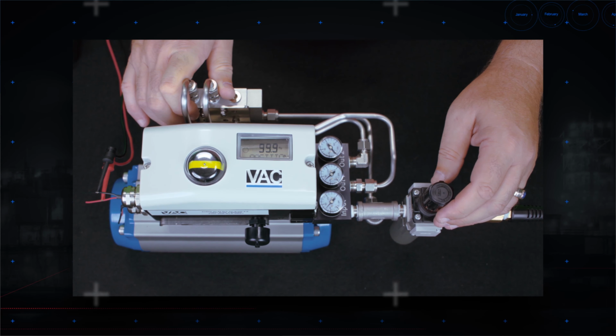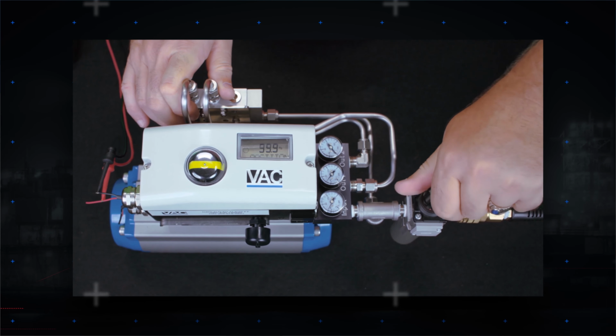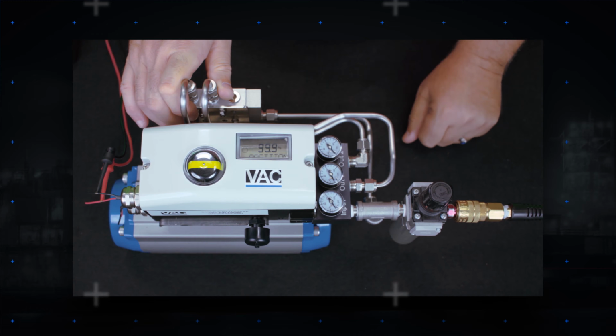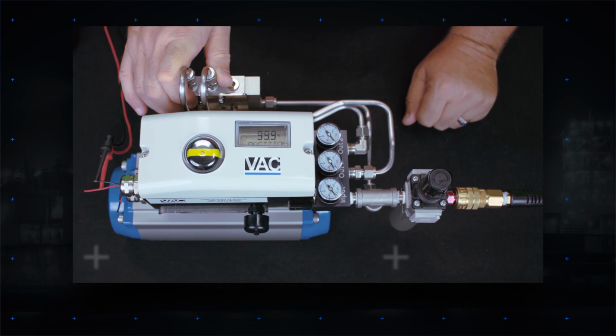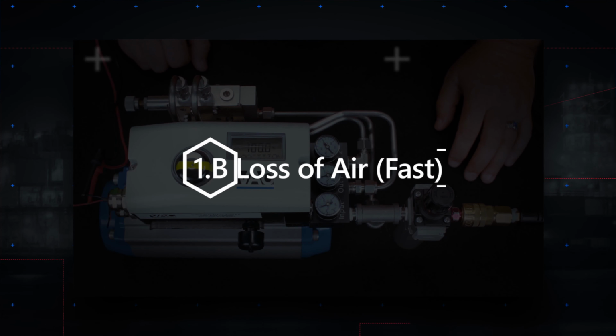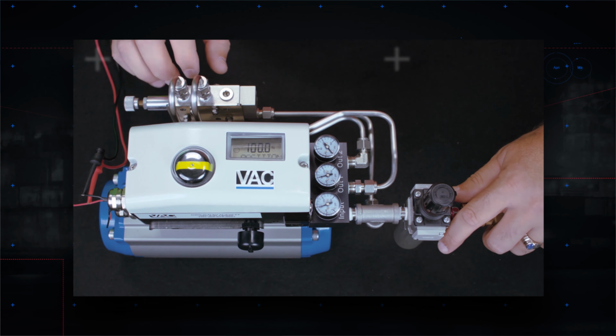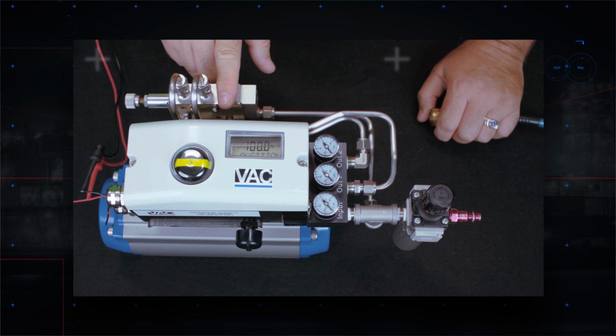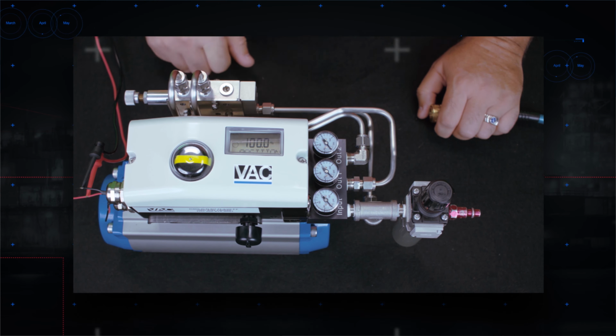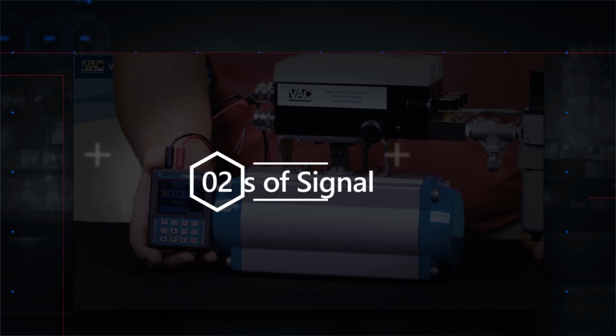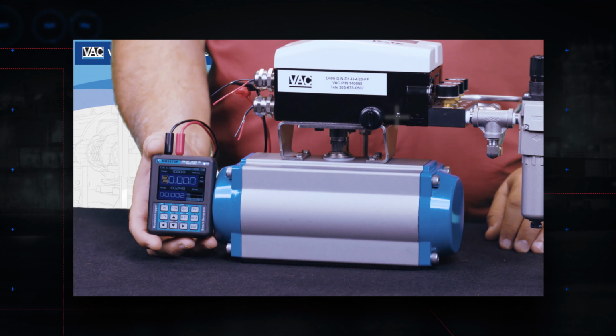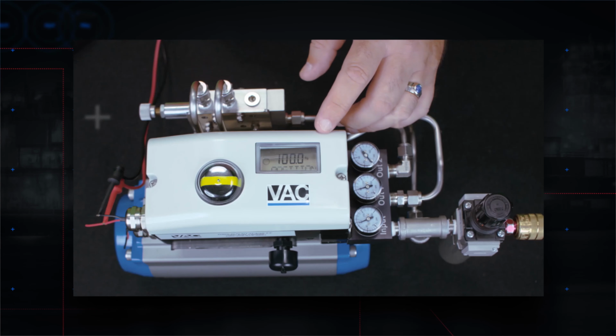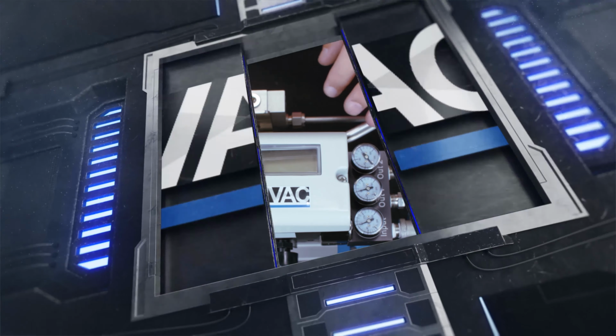When the air pressure is reduced slowly like this, the valve does not move when the supply pressure drops below the set point of the lockup valve. When the air is suddenly removed like this, the valve doesn't move at all before the lockup valve shifts to hold the valve in position. When the electrical signal is turned off like this, the valve also locks in place with no movement.